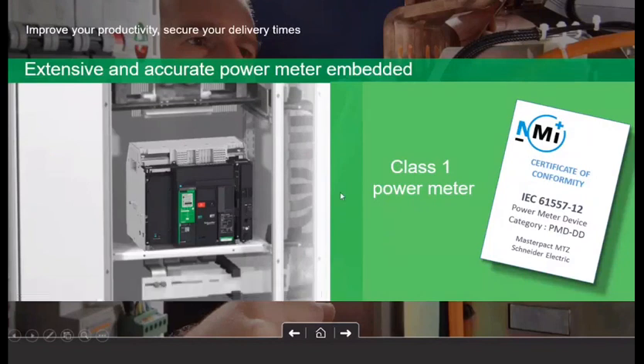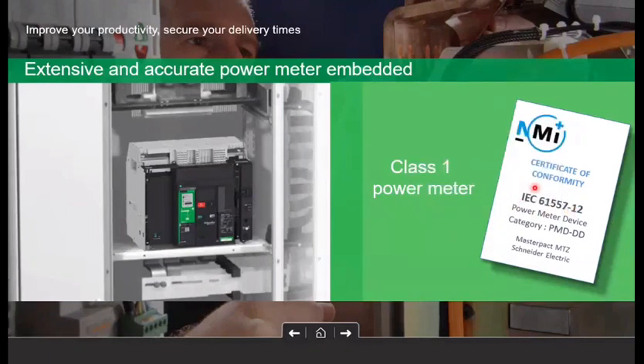Also, MTZ will give you the THDI and THDV values by default, and this class 1 energy accuracy is third party certified in accordance with IEC 61557-12. So this ACB is third party certified. One more important point, you can very well get rid of your CTs, external meters, and all the accessories related to the external CTs and meters.